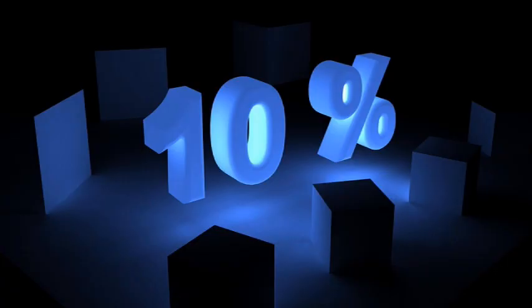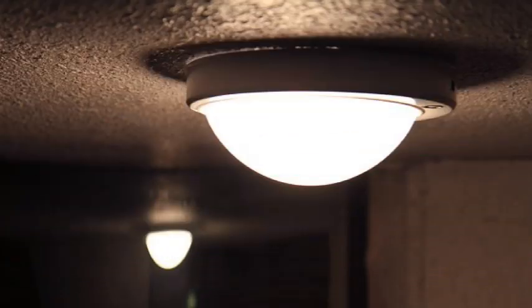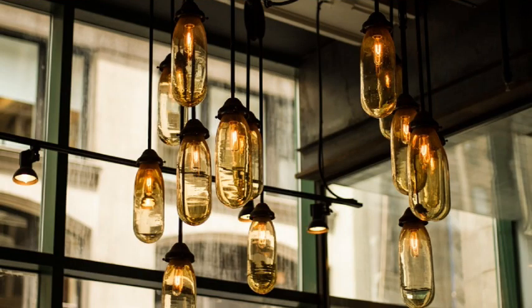Any of that new stuff would need to comply. Any new windows, if you change more than, I think it's 10% now, of the lighting in any space in an alteration, meaning when the code says space, it's not the entire space. The space is like an office within the unit. So if I change more than 10% of lighting in that space or that office, lighting compliance and the controls need to come up to current code.